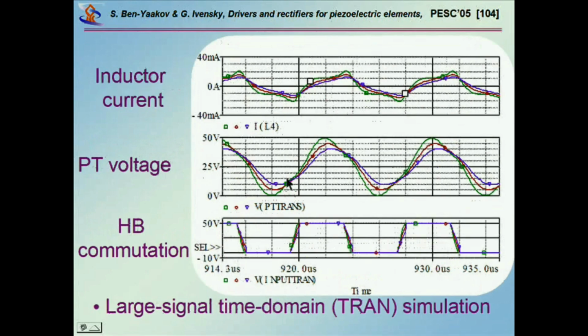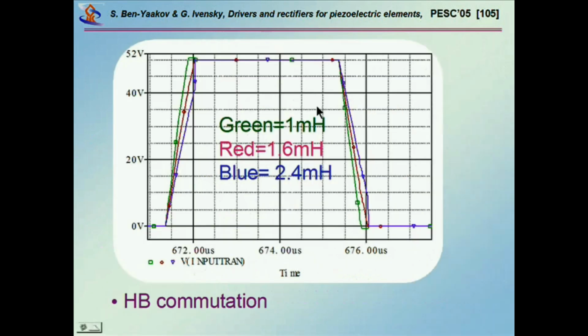And as you see, the waveforms are not too bad because you have a fine filtering, so the waveform is not bad at all. The current is far from being sinusoidal, though, but it's okay. There's no problem in that. And here we see the soft switching effect.